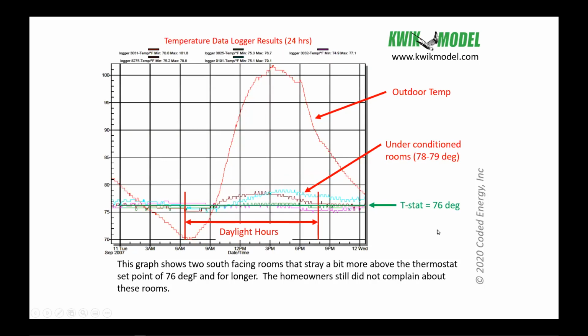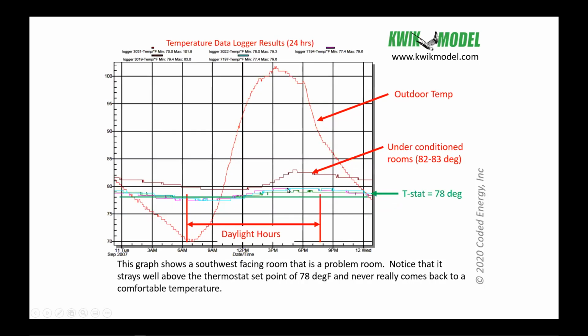Now, this was another house. They liked it at 76 degrees, and you can see this room is rising up a little bit, getting a little warmer. You can also tell which side of the house a room is on by when it peaks. If it peaks later in the afternoon, it's probably on the west side of the house. If it peaks earlier in the day, it's probably on the east side of the house, and so on. Okay, so you can kind of tell. So we got these rooms. Again, the homeowner did not complain about these rooms.